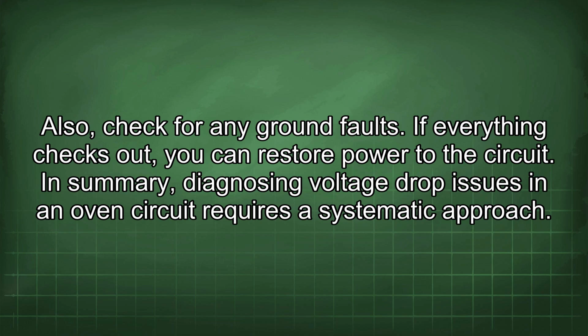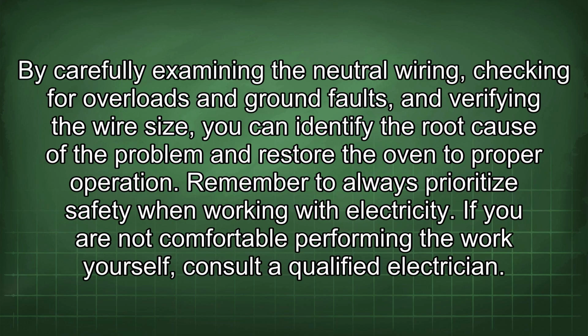In summary, diagnosing voltage drop issues in an oven circuit requires a systematic approach. By carefully examining the neutral wiring, checking for overloads and ground faults, and verifying the wire size, you can identify the root cause of the problem and restore the oven to proper operation. Remember to always prioritize safety when working with electricity. If you are not comfortable performing the work yourself, consult a qualified electrician.